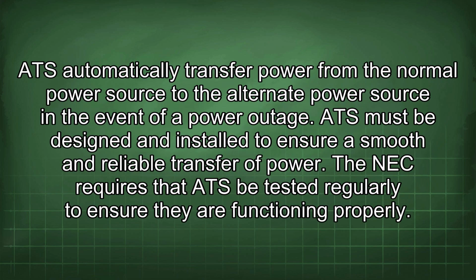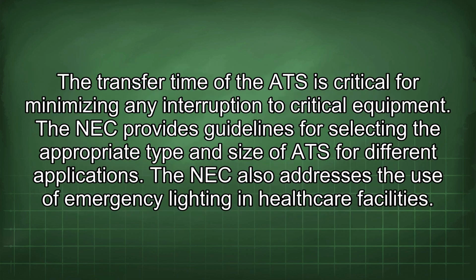ATS automatically transfer power from the normal power source to the alternate power source in the event of a power outage. ATS must be designed and installed to ensure a smooth and reliable transfer of power. The NEC requires that ATS be tested regularly to ensure they are functioning properly. The transfer time of the ATS is critical for minimizing any interruption to critical equipment. The NEC provides guidelines for selecting the appropriate type and size of ATS for different applications.